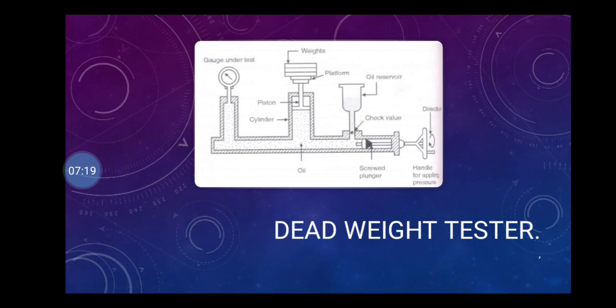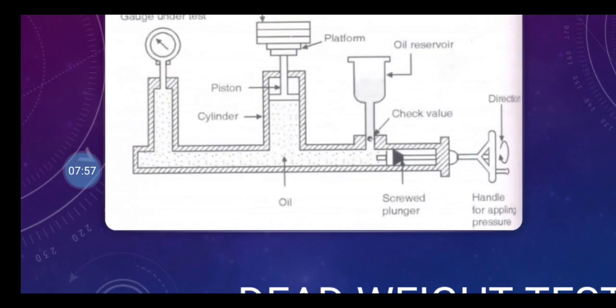As studied in the operation of all the types of the pressure transducer, the meters are to be calibrated to read in the desired unit. Calibration is needed. Input is the pressure to be measured, then primary transducer, then secondary transducer, then output, which is not directly a pressure value. This output is to be calibrated and accurately converted into pressure so that it is ready to be read by the meter. For most of the transducers, calibration is done by dead weight tester. This figure shows the actual operation of the dead weight tester.